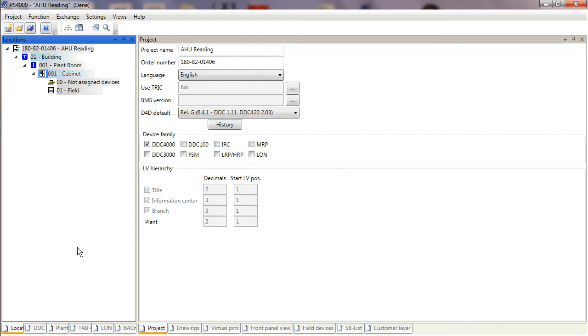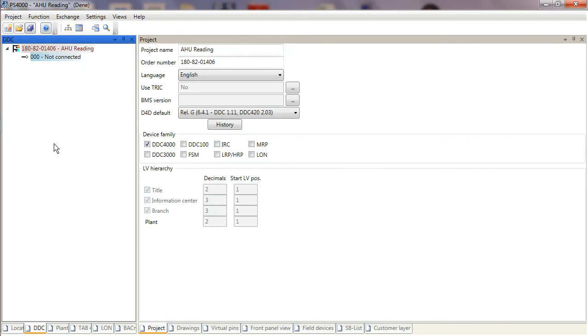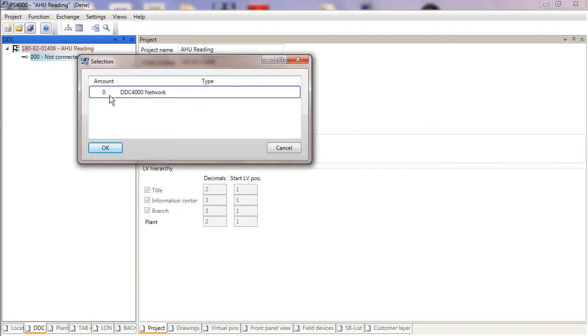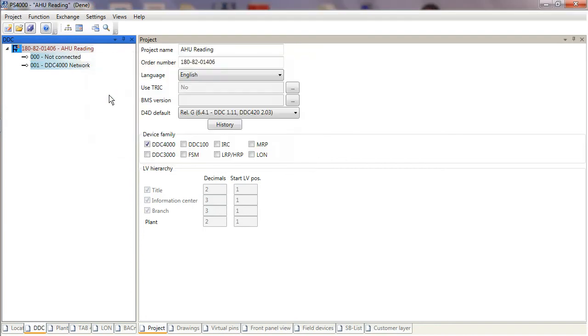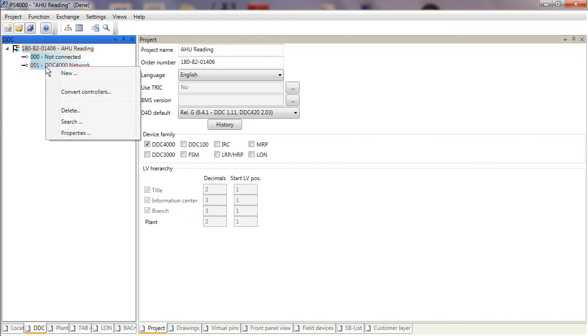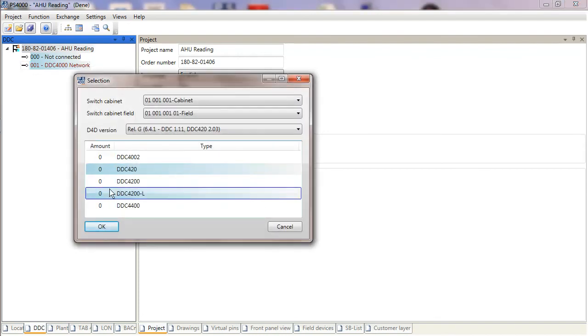I click on the DDC tab and then I right-click on the project title and select New. I can introduce the first thing, which is a network. The controller must sit on a network. If there are multiple controllers, they should all sit on the same network. If they're not in the same network, they won't be able to communicate, but they will still be in the same project file. On my network number one, I can now select New.